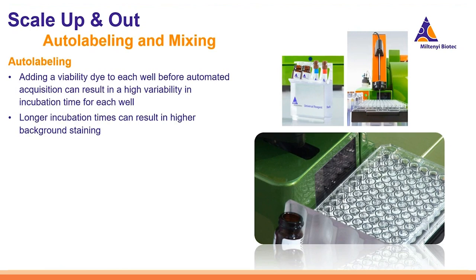Our MACSQuant has this needle arm that is used for acquiring from your single tube, your 96 rack, your multiple 5 mL FACS tubes, but this needle can also add reagents for you or auto label for you. It's basically a little liquid handling system. So imagine that you had something like 7AAD.